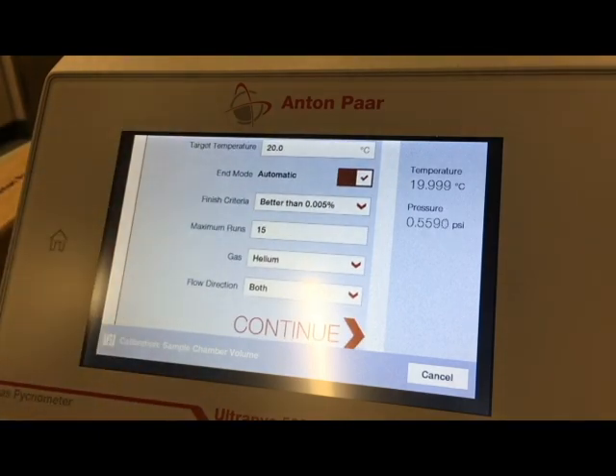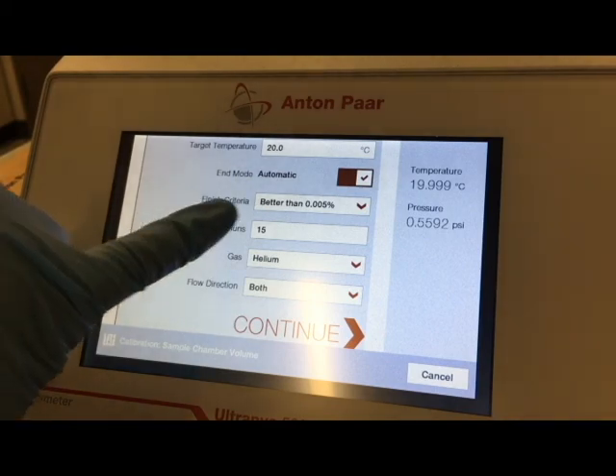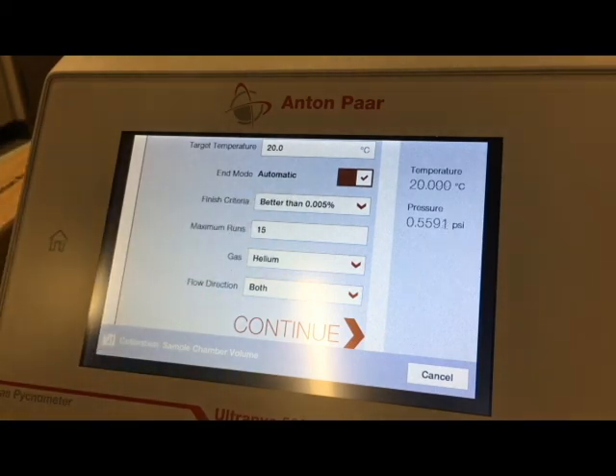Next is end mode. Automatic is the best option for this. This is going to take several data points, and it's going to stop the test when it has several data points that are within 0.005% of each other, meaning that you have 0.005% error. The maximum number of runs it will do is 15, just in case it takes a very long time. You're not having the test run forever. It will run either until it gets a 0.005% error in your answer, or it will do 15 runs.